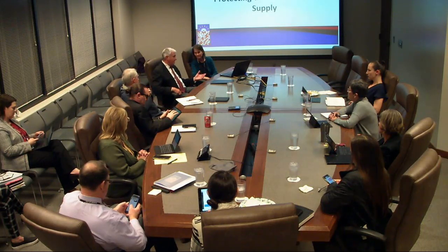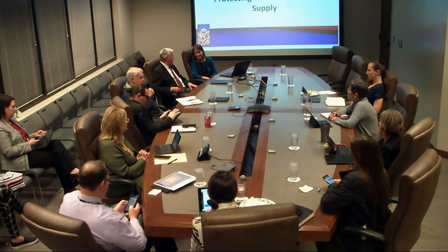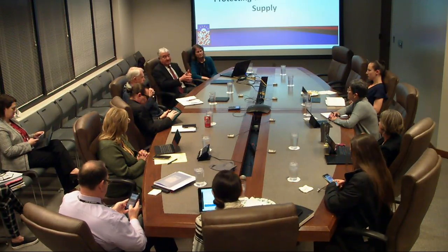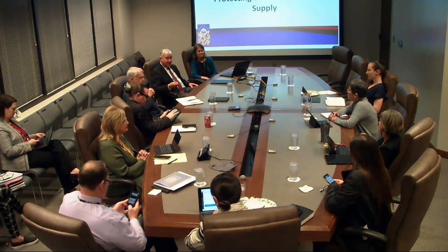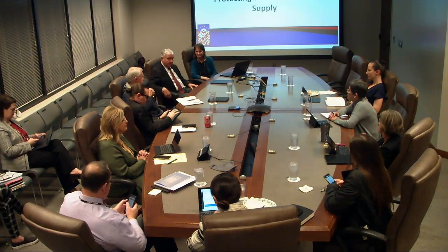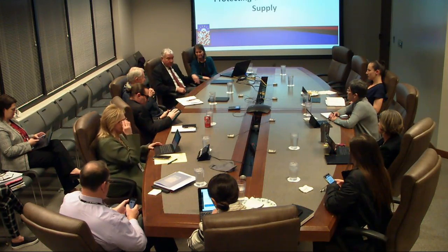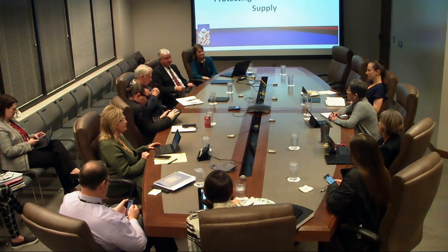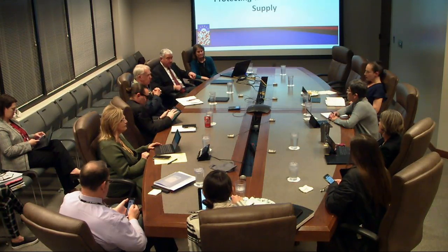It wasn't working right. That's how it didn't pass the test. The health department came in, yes. And so we said, no, just disconnect it. Physically, I want to see a gap between your irrigation or your well water or whatever it is, and don't attach it to your plumbing inside your building. That's all it was. There was nothing to test anymore. Just cut the piece of pipe out, turn this off, and turn this one on.